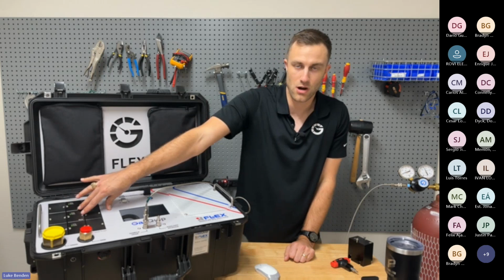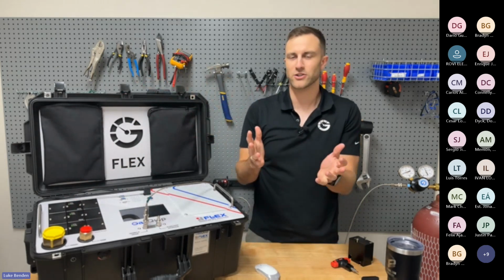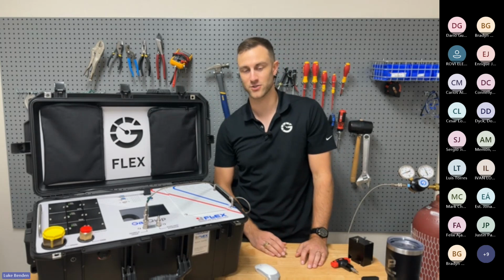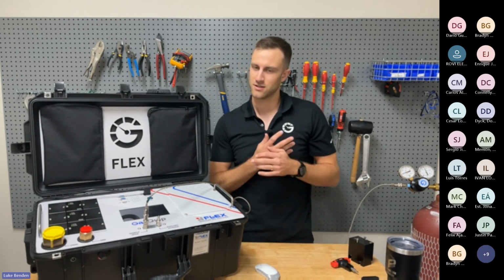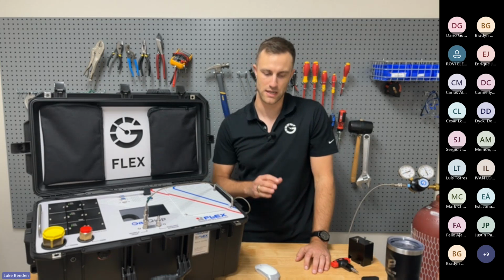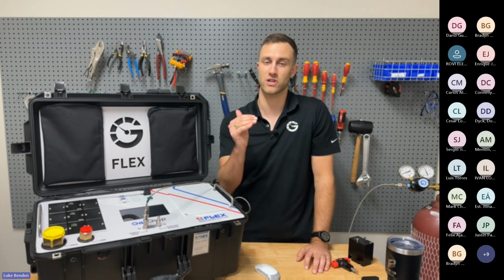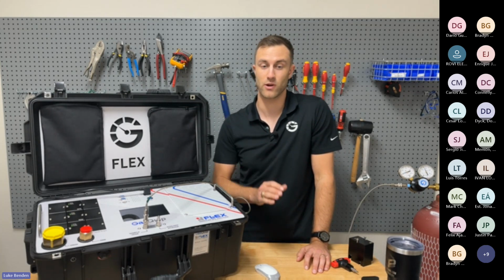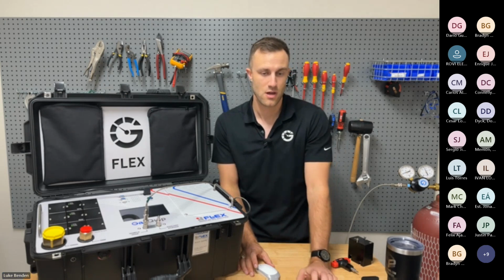H2S is every 1 year. That is a manufacturer recommendation. You can push that as far as you'd like. If your device is still reading good, you're testing against calibrated gas and you're still getting good values, that's up to you, but that's what we recommend because the sensors tend to drift over time. So that's what we recommend as far as replacing those.